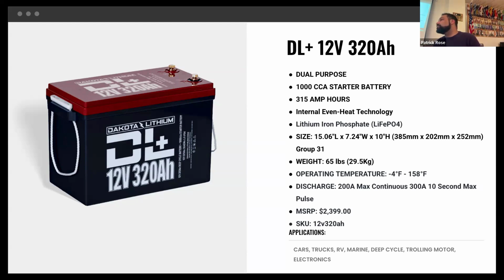So what do you recommend? Because 300 amps is a high current. A common pattern for 100 amp hour batteries, which are a common unit for making a battery bank, is to put a 100 amp MRBF fuse on each terminal. But obviously with a 300 amp hour battery with 300 amp discharge, or 1,000 amp discharge, you're not going to put a 1,000 amp, 1C rated fuse on that. How do you reconcile the theoretical current capacity it can discharge at with safe fusing? What do you think about that?